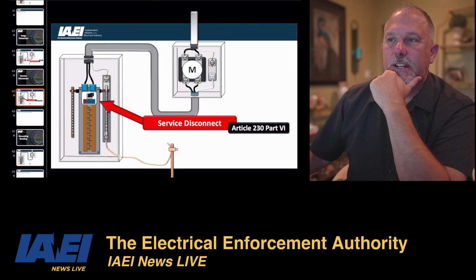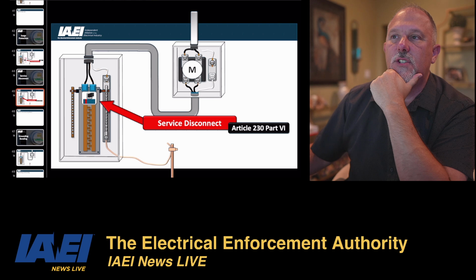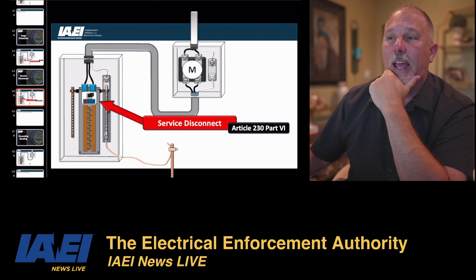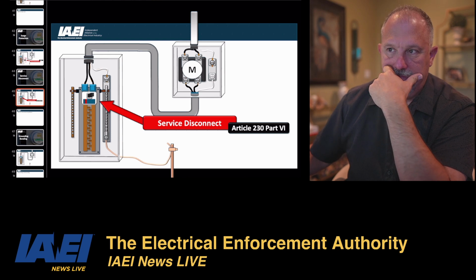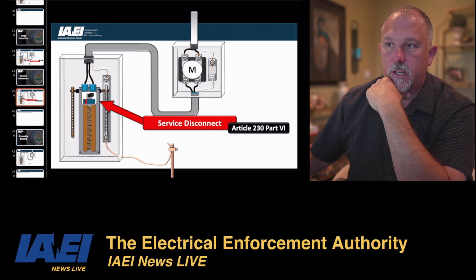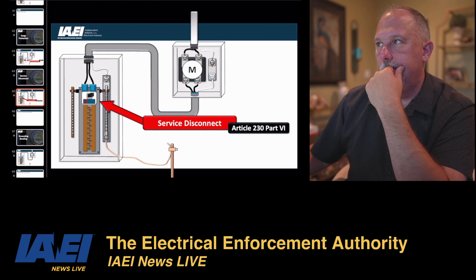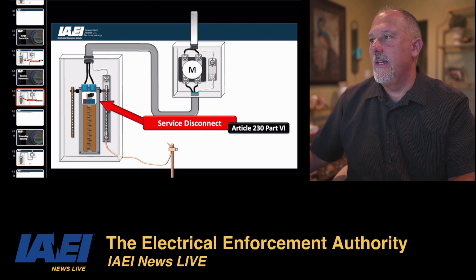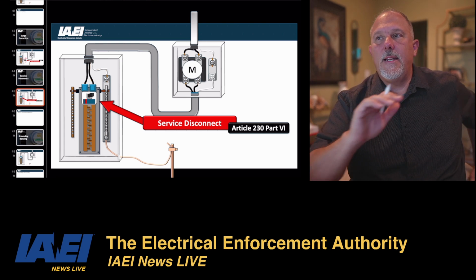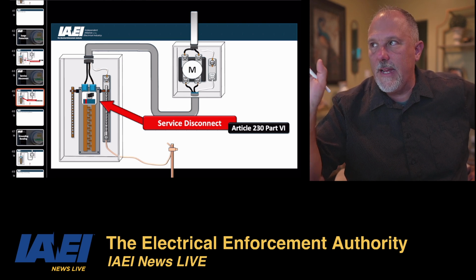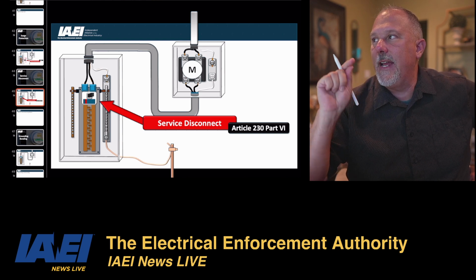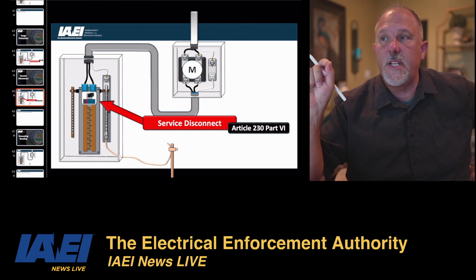There was a section in here that said service equipment had to be marked as suitable for use as service equipment. And that is misleading. So in 230.66A, and this is what sort of threw me off last week, it says service equipment rated 1,000 volts or less shall be marked to identify it as being suitable for use as service equipment.